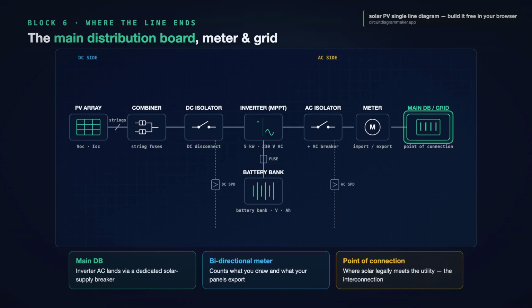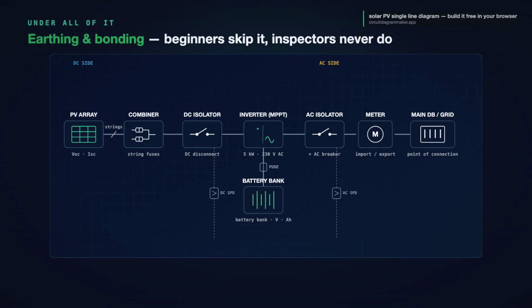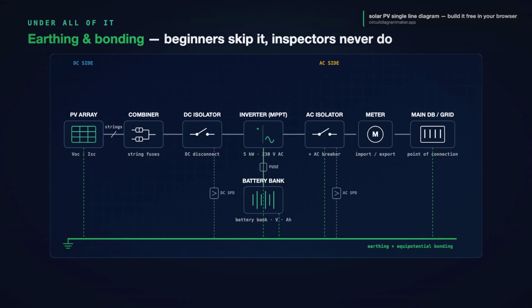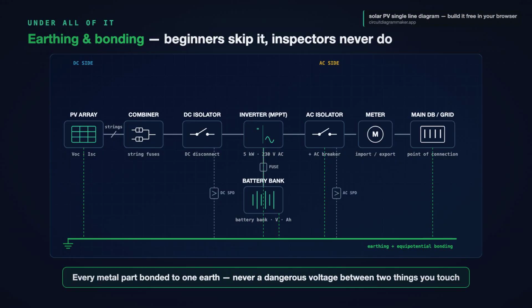And running underneath all of it, earthing and bonding, the part beginners skip and inspectors never do. Every metal part that should never be live gets connected to earth. The panel frames, the mounting rails, the inverter body, the isolator enclosures, all bonded together and tied down to the earthing system. On the single line diagram, this shows up as a green line or an earth symbol, reaching every block. Equipotential bonding just means all that metal is held at the same potential, so there is never a dangerous voltage between two things you might touch at once. It is the quiet safety net under the entire drawing, and on a solar SLD, it is not optional. Draw the earth every time.